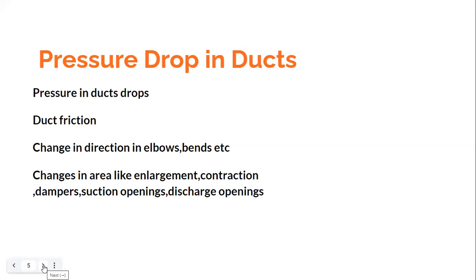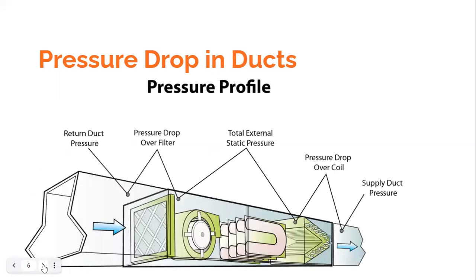This pictorial representation of external static pressure shows the AHU, including the coil and filters which also result in pressure drops. There will be a pressure drop in the return duct, in the supply duct, across the filter, and across the coil. All these pressure drops must be considered when sizing the duct.